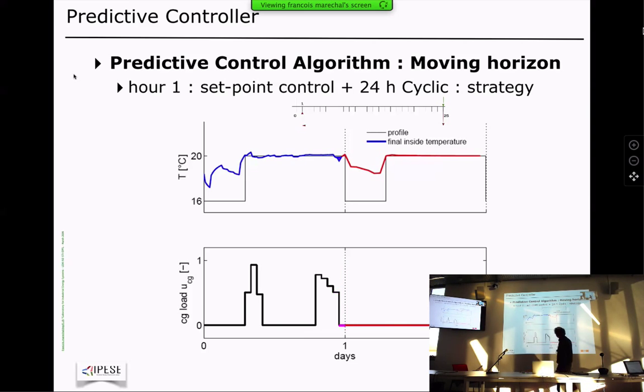So you can see what I have finally done. I started at 75%, and then progressively stopped the unit in reality, which was different from what was predicted. It seems the system tried to push to the limit because the temperature has been lower than the set point, so the building has been cooled. It seems that in order to limit cost, the system decided to stop a little too early. But nevertheless, what you've seen is that I defined a strategy of operation. You can see the system reacting, and has finally filled the tank and sent the heat to the building.